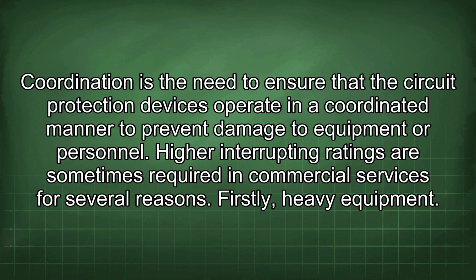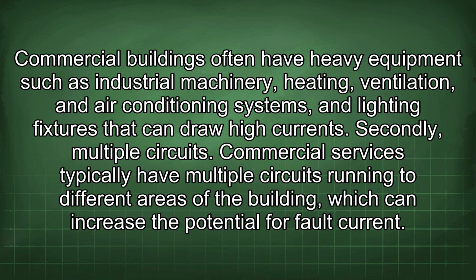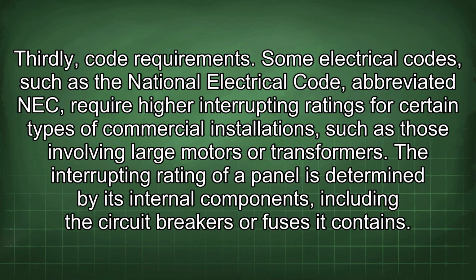equipment or personnel. Higher interrupting ratings are sometimes required in commercial services for several reasons. Firstly, heavy equipment. Commercial buildings often have heavy equipment such as industrial machinery, heating, ventilation, and air conditioning systems, and lighting fixtures that can draw high currents. Secondly, multiple circuits. Commercial services typically have multiple circuits running to different areas of the building, which can increase the potential for fault current. Thirdly, code requirements. Some electrical codes, such as the National Electrical Code, abbreviated NEC, require higher interrupting ratings for certain types of commercial installations, such as those involving large motors or transformers.